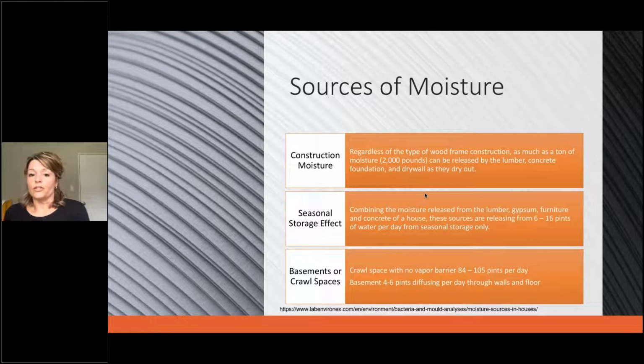So there's a lot of sources of moisture. Construction moisture is the first and foremost that we need to deal with in new construction, especially if we're closing up a building in late spring or summer. We're going to have to deal with a lot of wet materials, not necessarily wet because they were rained on, but because they've absorbed a lot of moisture from sitting in exposed high dew point conditions.